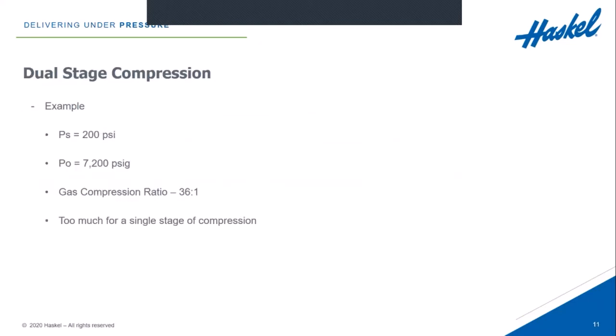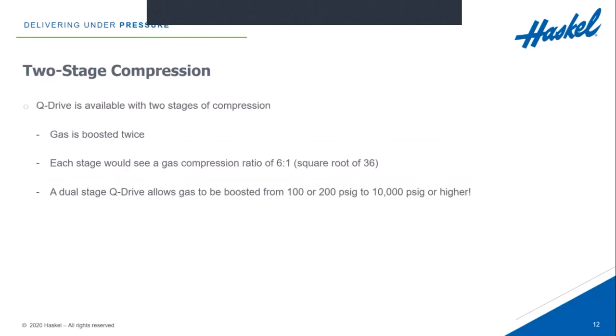Here's an example. If you have a gas supply pressure of 200 PSI and you want to get that gas up to 7,200 PSI, dividing 200 into 7,200 gives a gas compression ratio of 36 to one — too much for a single stage on any compression system. However, the Q-Drive is available with two stages of compression on a single piece of equipment. Each stage would see a gas compression ratio of approximately six to one, which is the square root of 36. So a dual-stage Q-Drive allows gas to be boosted from just 100 or 200 PSI all the way up to 10,000 PSI or higher on two stages on a single piece of equipment.